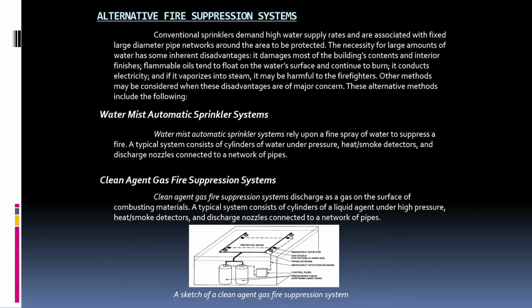The second one is clean agent gas fire suppression systems. Clean agent gas fire suppression systems discharge as a gas on the surface of combusting materials. A typical system consists of cylinders of a liquid agent under high pressure, heat or smoke detectors, and discharge nozzles connected to a network of pipes.